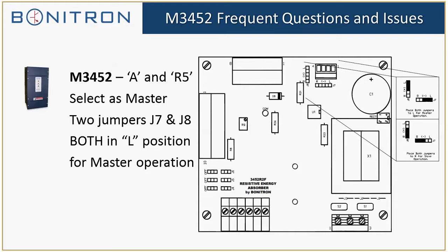The 3452 has a variety of control boards that are offered. The most basic ones are the A control board and the R5 control board. These have very limited statuses which they output, mainly just a ready output. By far, the most common question I get on these is when they go to start it up, nothing happens and the drive faults out. Typically this occurs because the unit has not been set as a master for standalone operation.